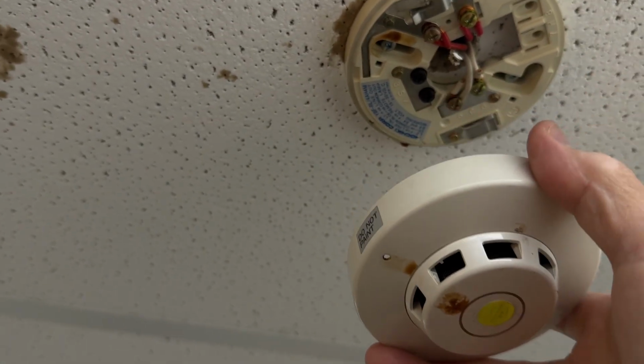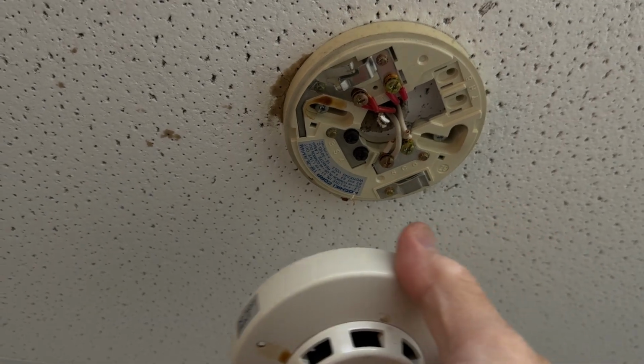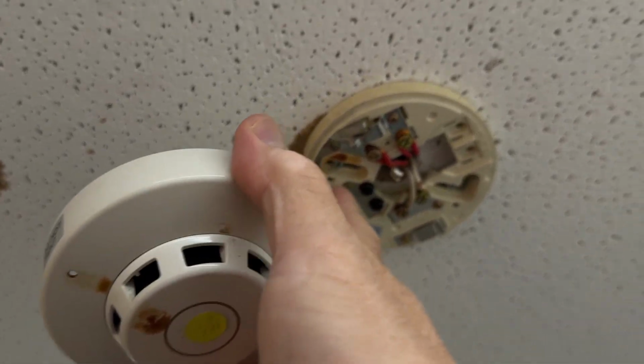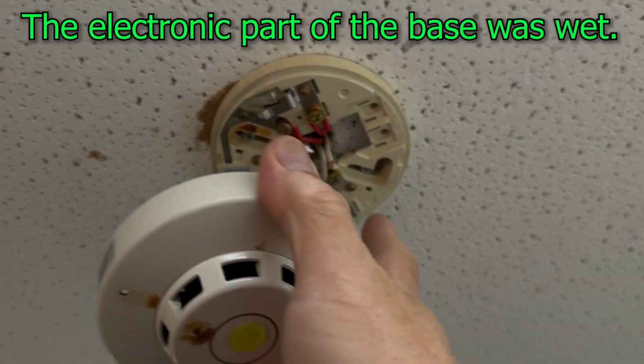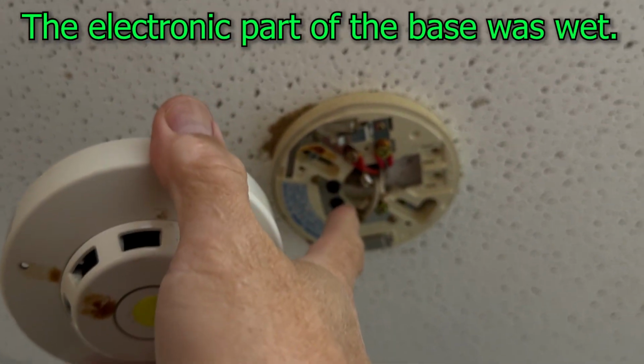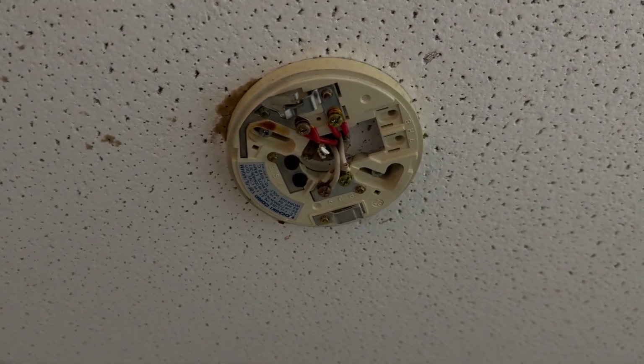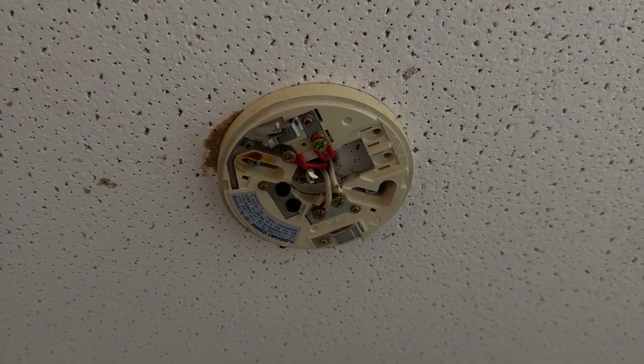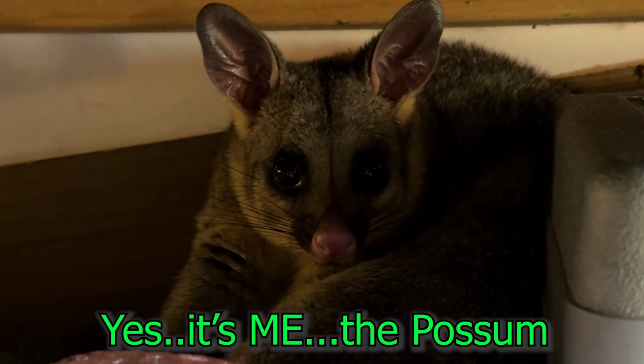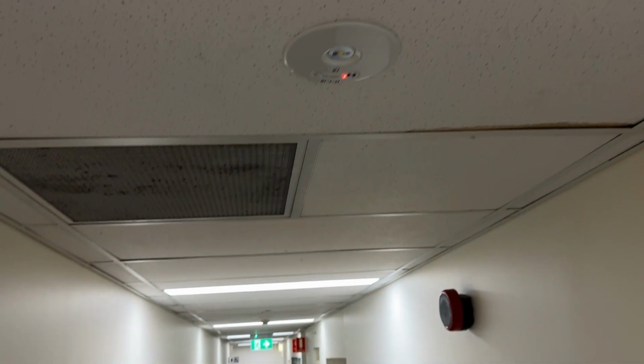So what does it mean? The way I see it, the alarm came from the actual base. The base got wet from, make a guess. Yes, it's possum. There's possum inside the ceiling space.